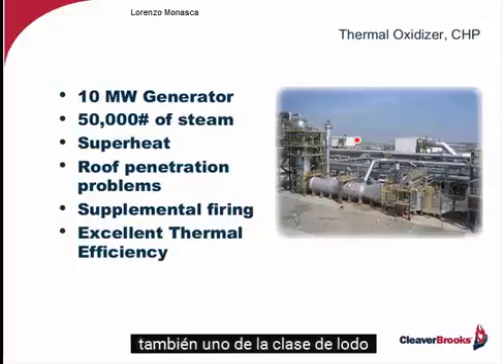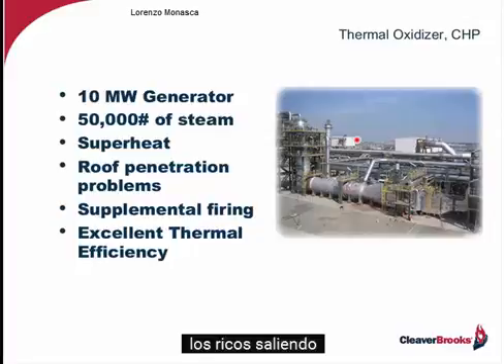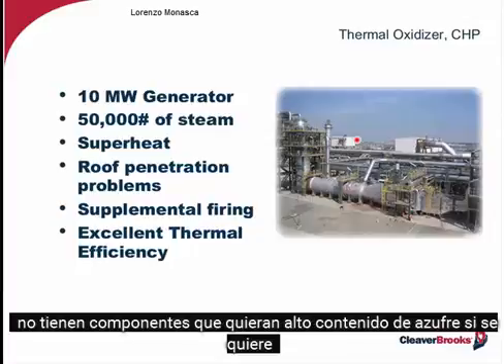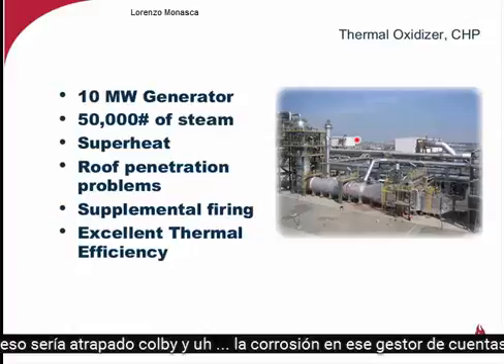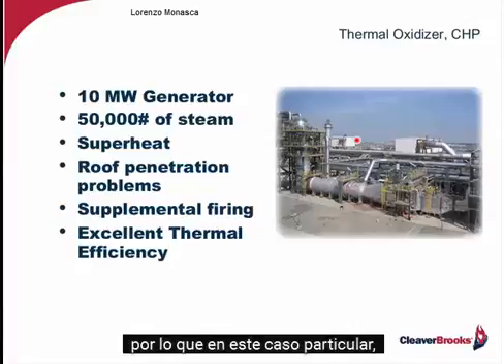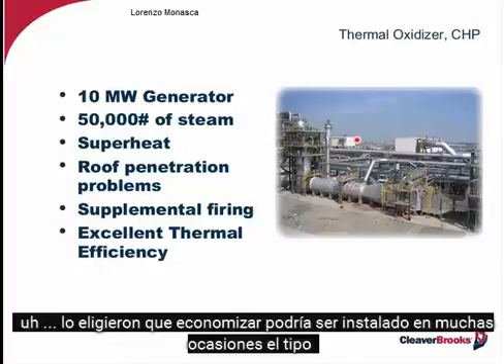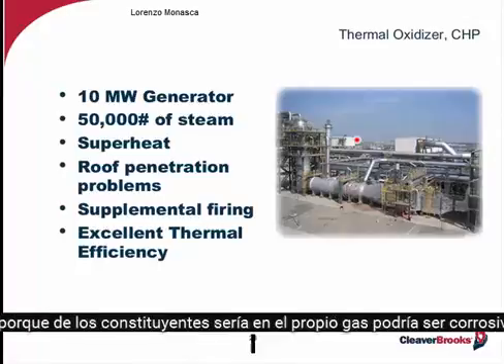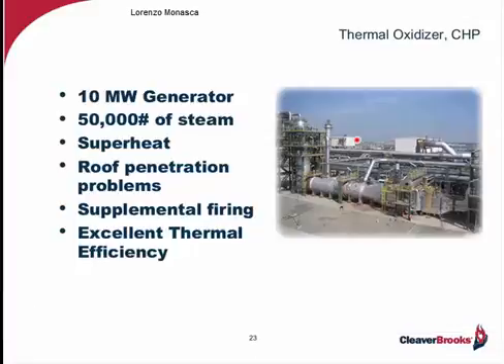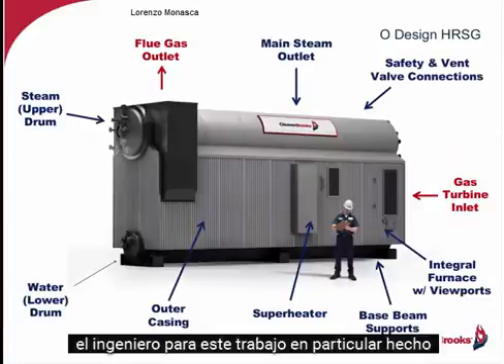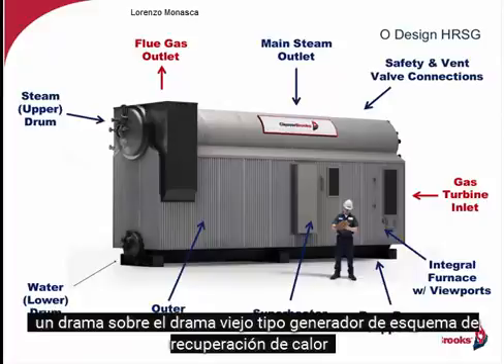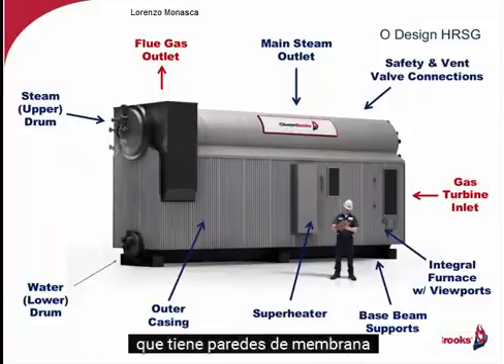They also wanted an economizer. And when it was looked at, the effluent coming off of the thermal oxidizer did not have constituents, like high sulfur, if you will, that would cause cold end corrosion on that economizer. So in this particular case, it was elected that the economizer could be installed. Many times economizers are not used with thermal oxidizers because of the constituents within the gas itself that could be corrosive. So the engineer for this particular job then selected a drum-over-drum O-type heat recovery steam generator. It has membrane walls. It also has a furnace.